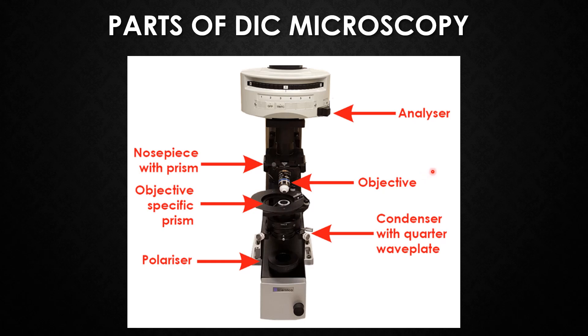The first part is the polarizer. The polarizer is inserted in the microscope train between the incandescent illumination source and the condenser. This component is designed to produce linearly polarized or plane polarized light, which is necessary for interference detection. To provide more image contrast adjustment, some DIC kits use a rotating polarizer and a quarter wavelength retardation plate, and the contrast is perfectly adjusted so the image of the specimen will have a three-dimensional effect.